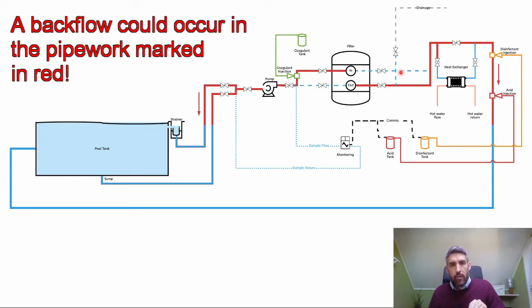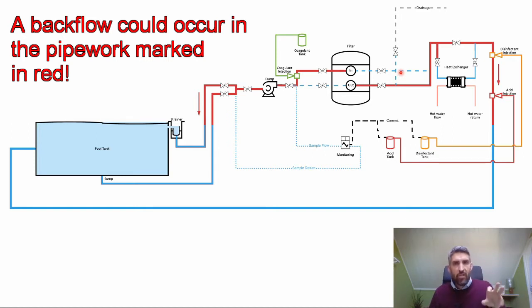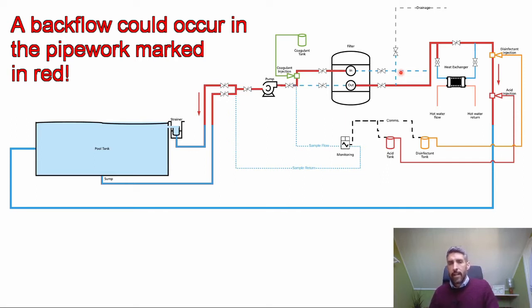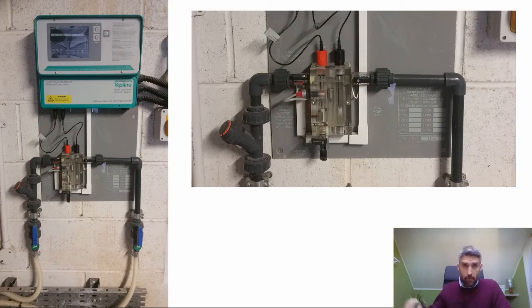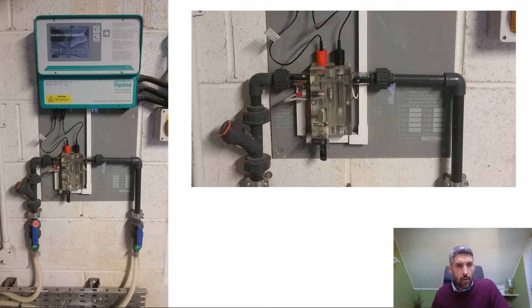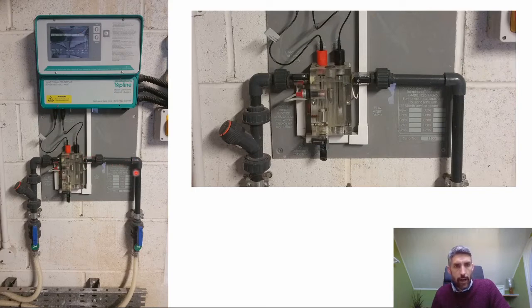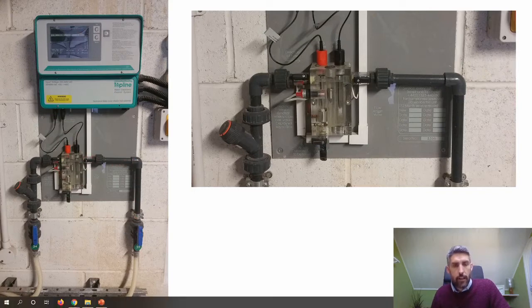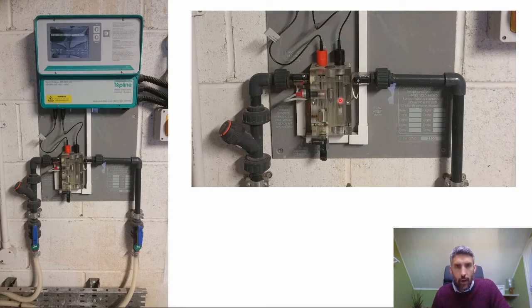You can still get a situation where the circulation potentially stops either through a power cut or because it's been manually shut down for backwashing, and yet the chemical dosing system continues to pump chemicals. There have been cases of this happening on these automatic dosing systems. Usually what you'll get is an interlock between the circulation flow going around the system and the sensor in a chemical dosing system.